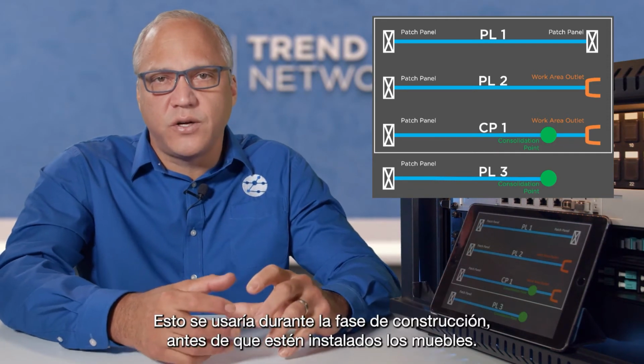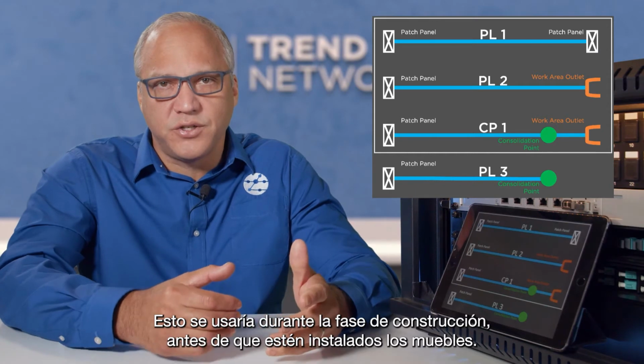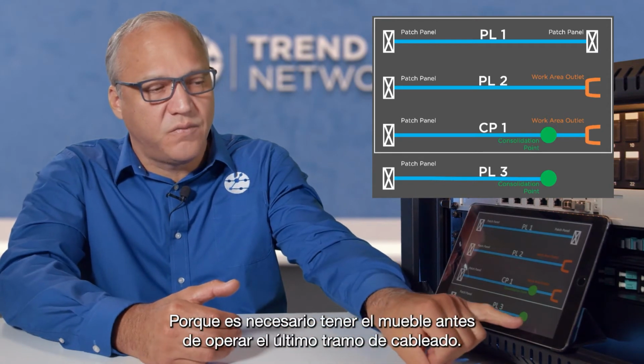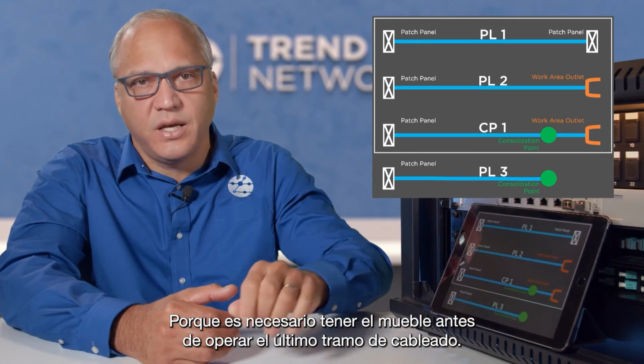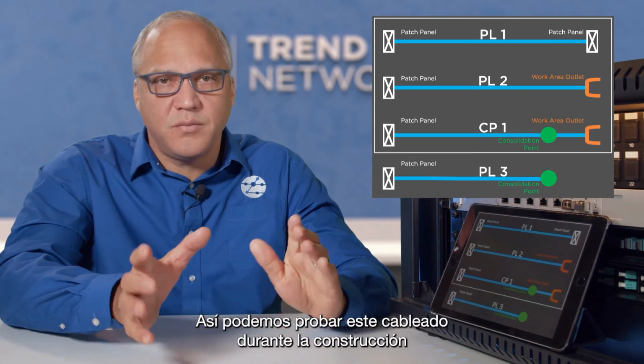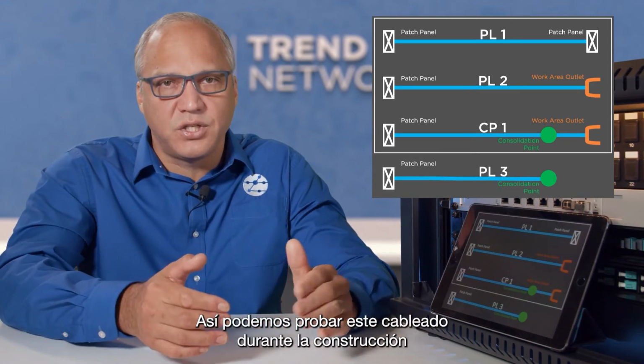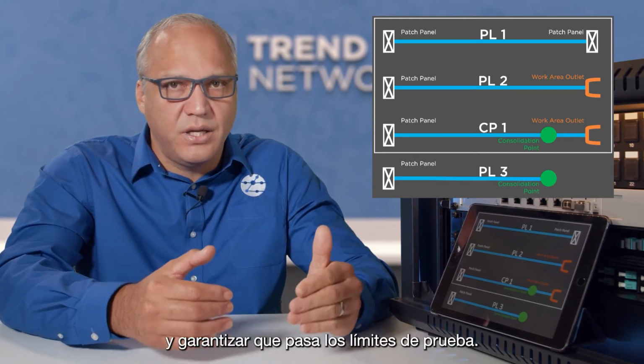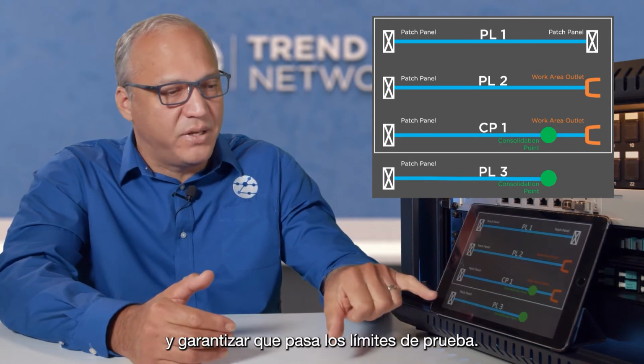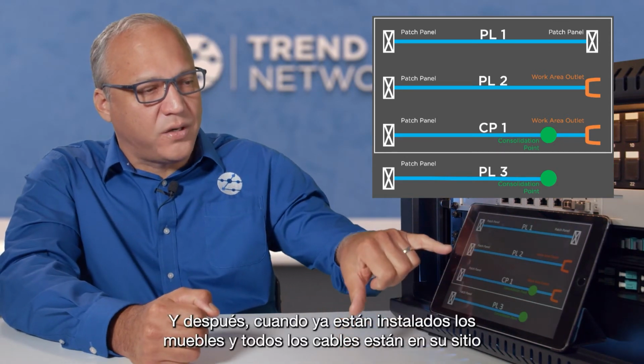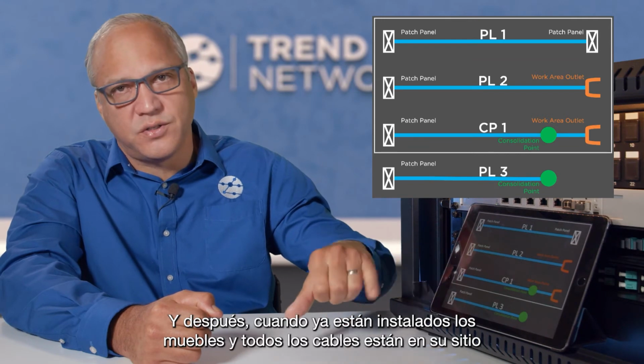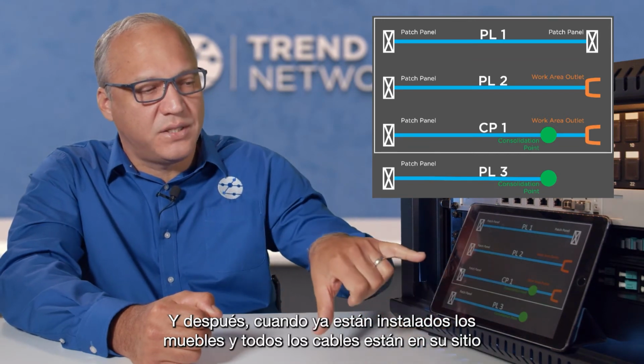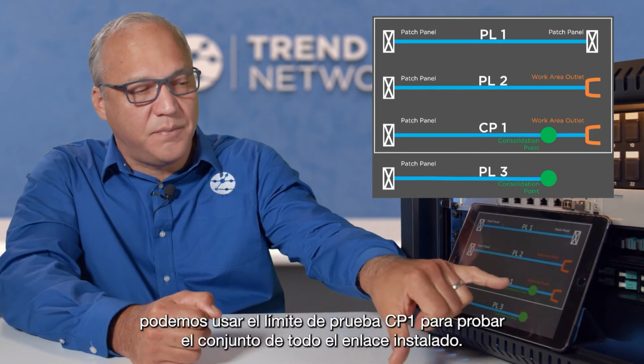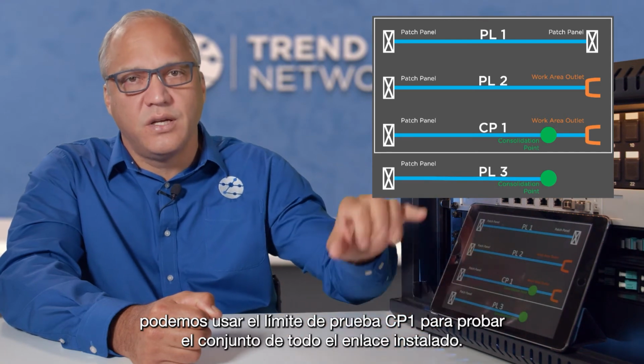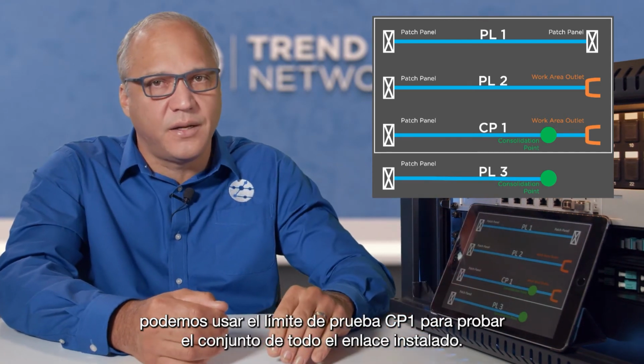So this would be used during the construction phase before furniture is in place because you need the furniture to run that last bit of cabling in, so that this cabling can be tested during construction, ensured to be passing test limits. And then afterwards, when the furniture is installed and the last piece of cabling is in place, then the CP1 test limit can be used to test the whole installed link.